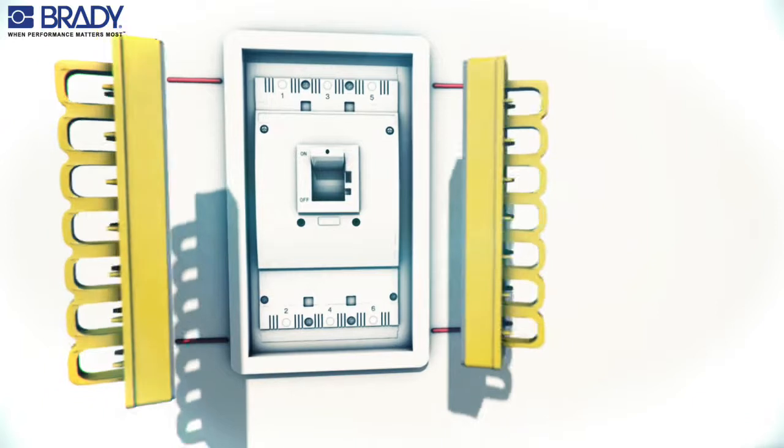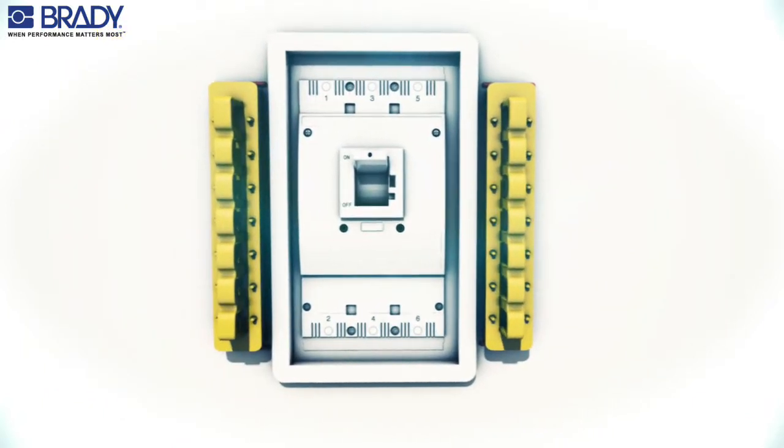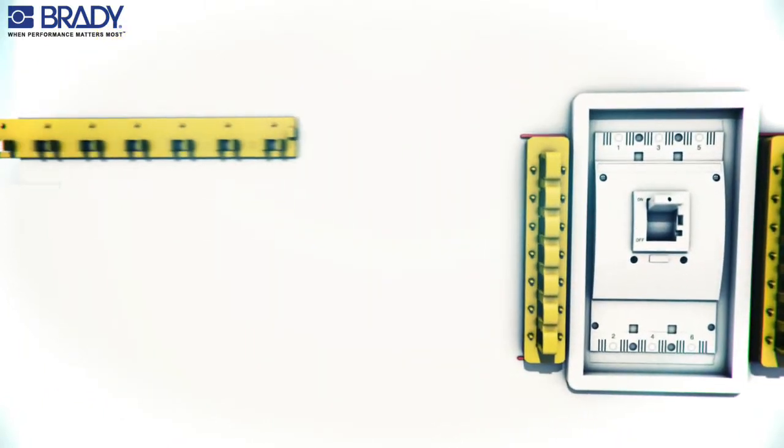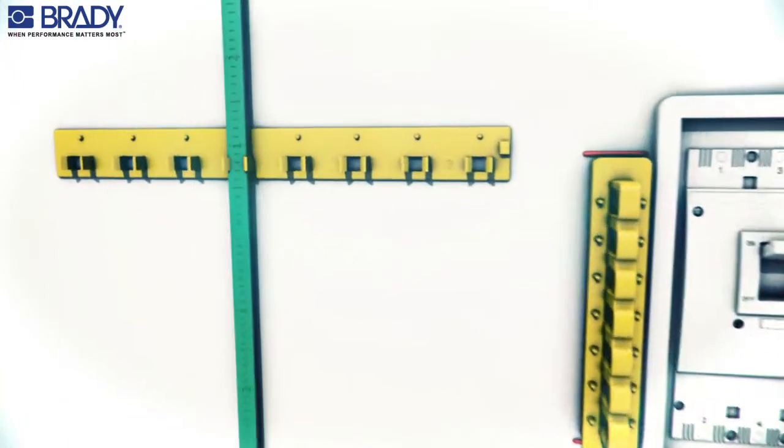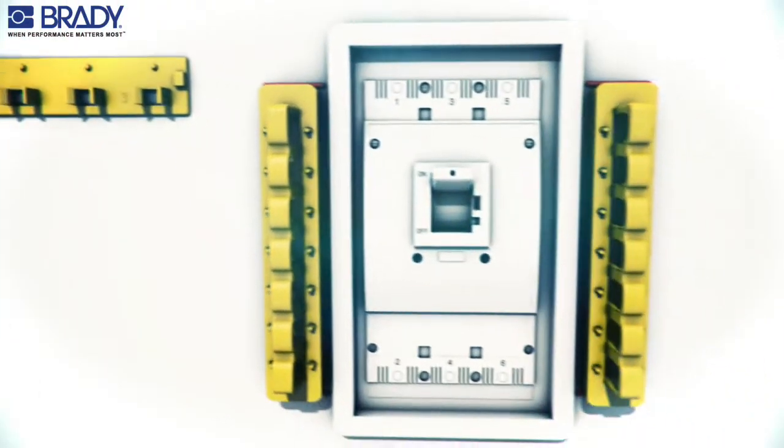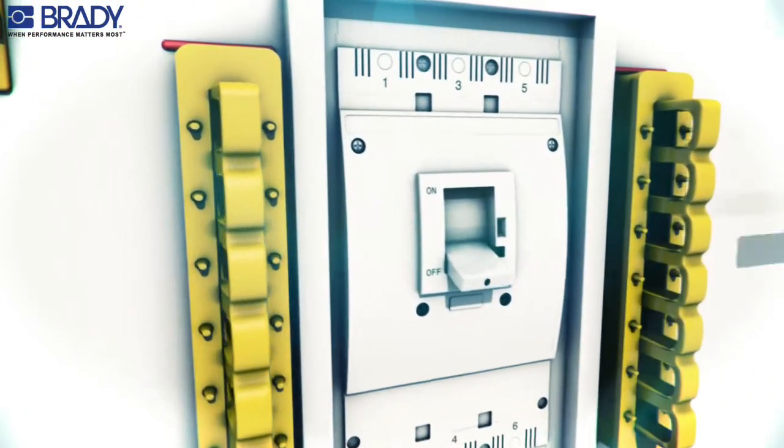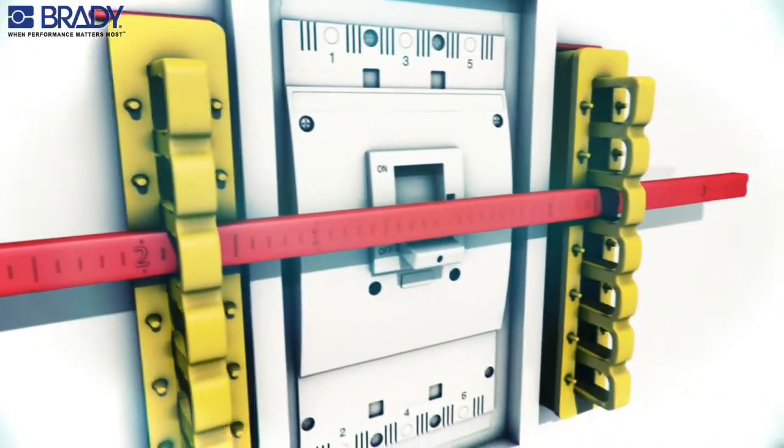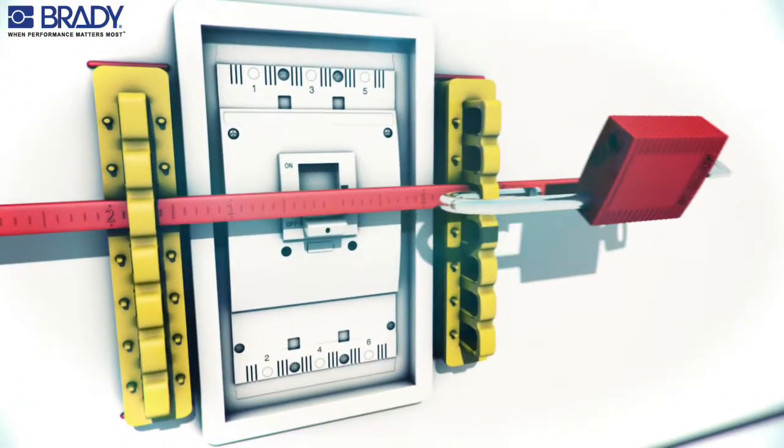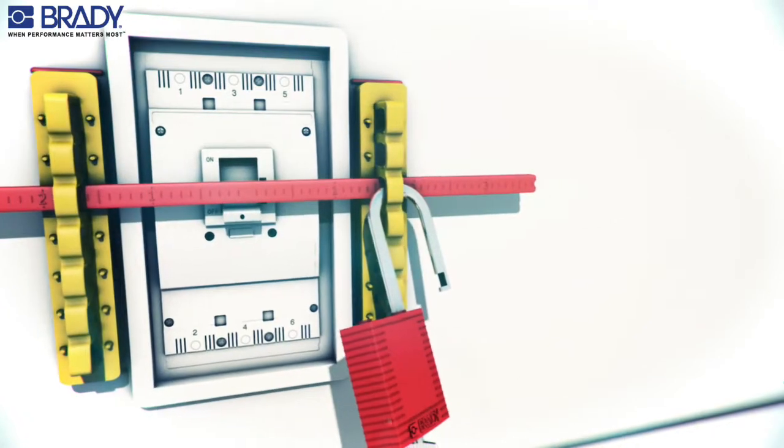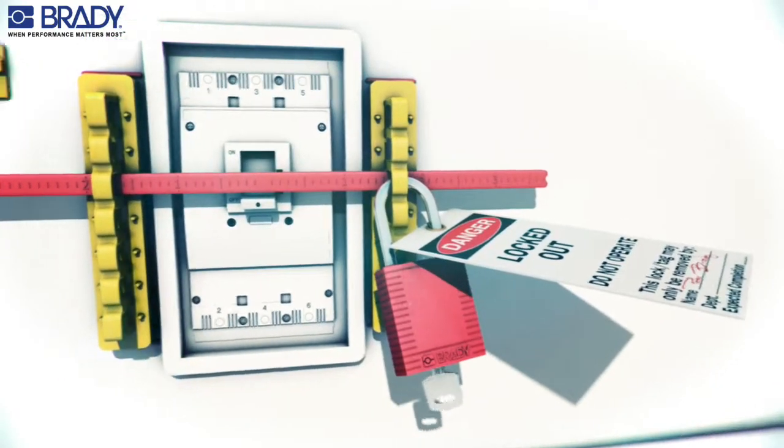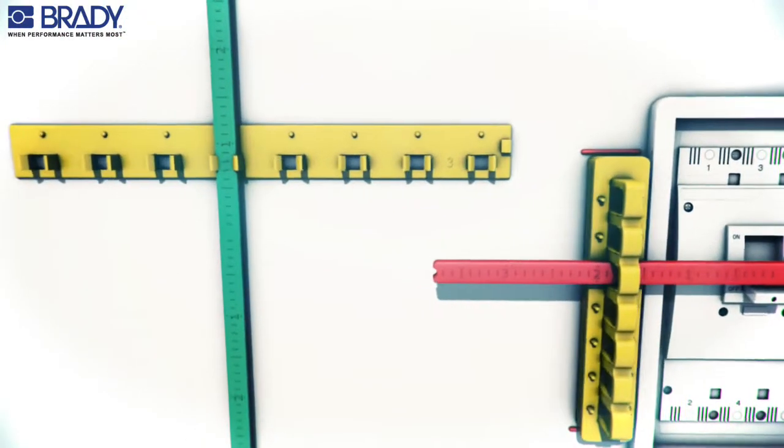Place the rails onto the clean surface. Place the blocking bar holder on the switch panel to store the unused blocking bars. To block the switch in the off position, place the red blocking bar and insert a padlock with a tag in one of the yellow bars at the red bar level.